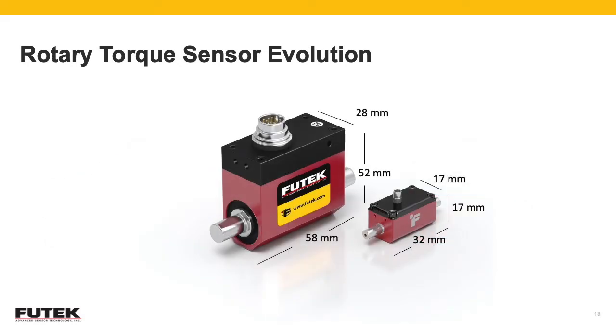This is the part we're quite excited to share with you today because we've been able to design a micro miniature rotary torque sensor. And this is one of the smallest footprints you'll find available in the market today. Here we have the same model I showed you in the previous slide stacked against our latest micro miniature rotary torque sensor, model QTA163. It's a 1 Newton meter micro rotary torque sensor with a 17mm by 17mm by 32mm housing with a 5mm shaft, capable of up to 150 RPM while achieving plus and minus 0.1% nonlinearity or better.